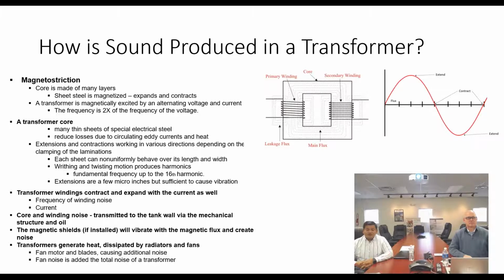How is sound produced in a transformer? Transformer core noise is caused by a phenomenon called magnetostriction. In very simple terms, this means that if a piece of magnetic sheet is magnetized, it can extend and contract by itself. A transformer is magnetically excited by alternating voltage and current, so it expands and contracts twice during the full cycle of magnetization. That means the frequency of core vibration is 2 times the frequency of the current applied. So we apply 60 hertz current, and the vibration on the core is 2 times the frequency. That means it vibrates at 120 hertz.